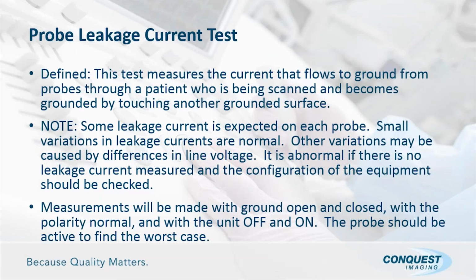Probe leakage current tests. As I said earlier, very few hospitals that I've visited actually go out and physically test all their probes. And I don't understand why. I think this is a very critical portion of electrical safety when it comes to ultrasound. Again, this is where the probes are actually physically contacting the patient. You know, the patient doesn't normally touch the ultrasound system. So as far as risk to the patient goes, this is where you have the highest possibility of harming a patient. So what is probe leakage?